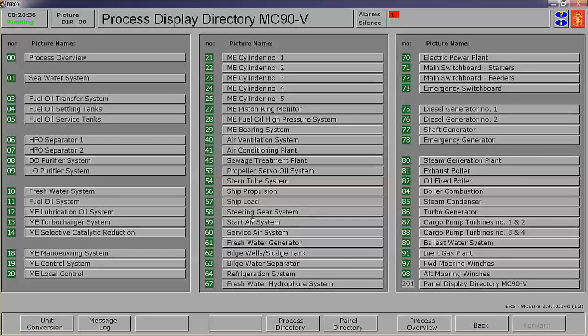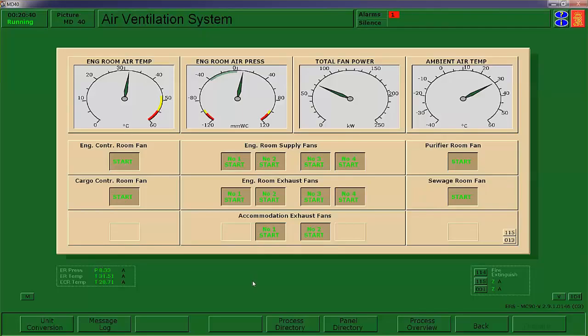Let's go look at our ventilation. We're still on a positive on the ventilation, so we're good there. By the way, we will have to keep an eye on this because as this ramps up, that's going to go into the negative, and we'll need to shut down these two exhaust fans. Your turbochargers are the biggest exhaust fans that you have in the engine room, and as those spool up, your engine pressure will drop down, and you have to turn off the exhaust fans.